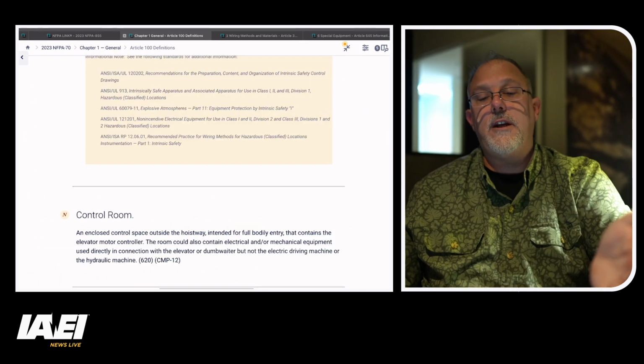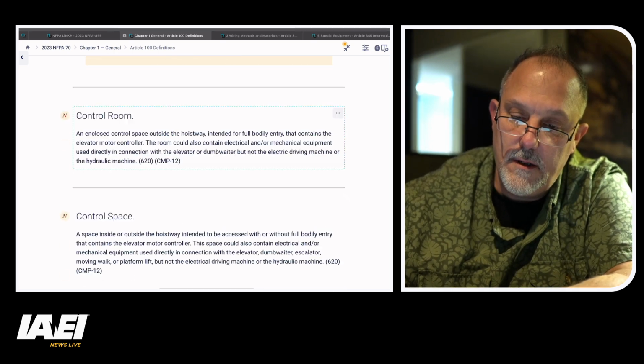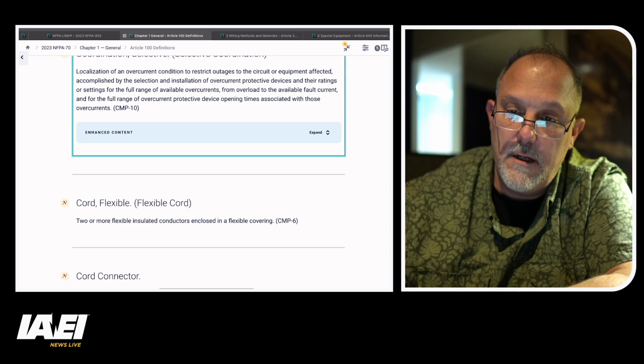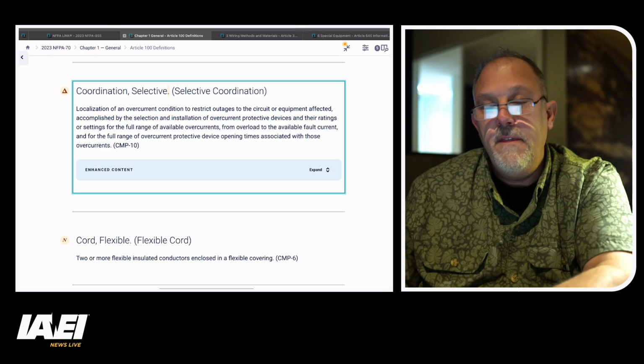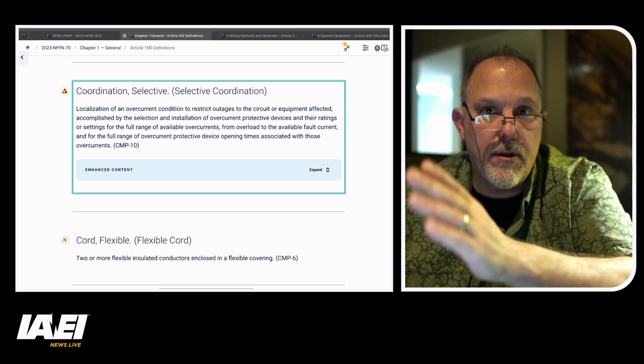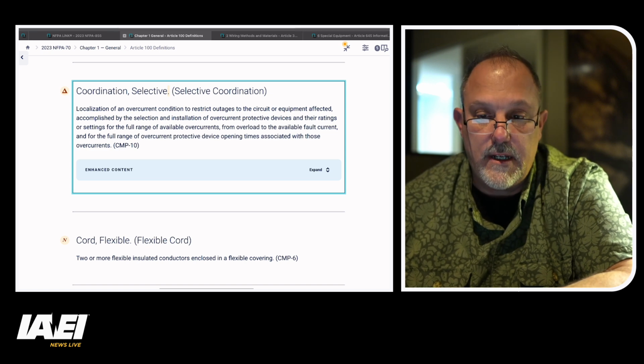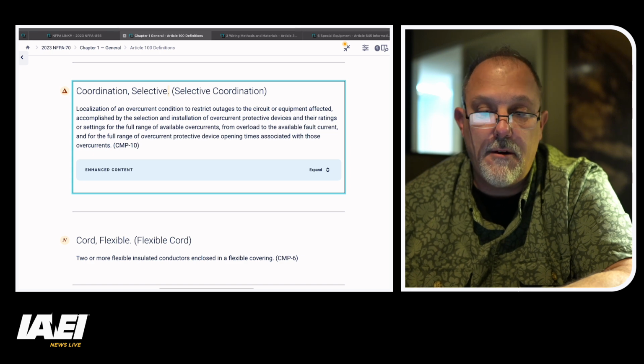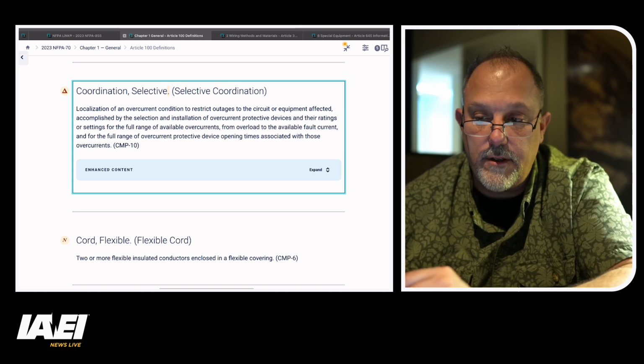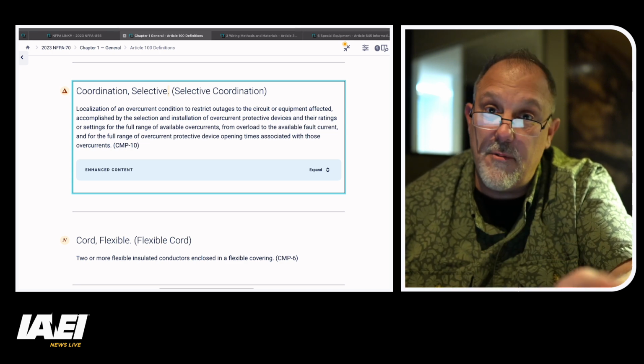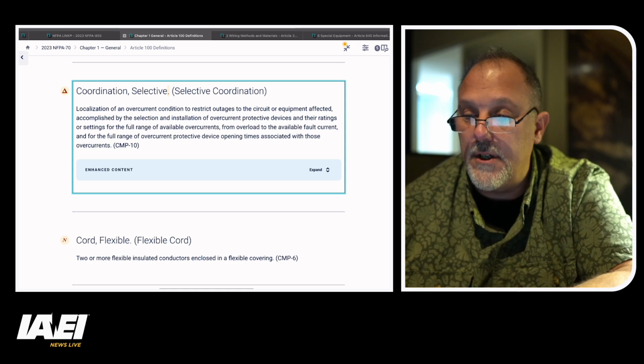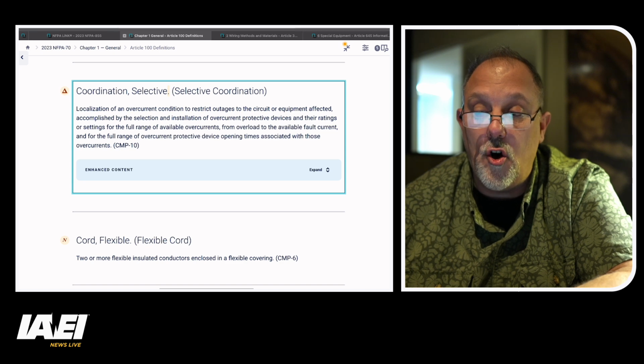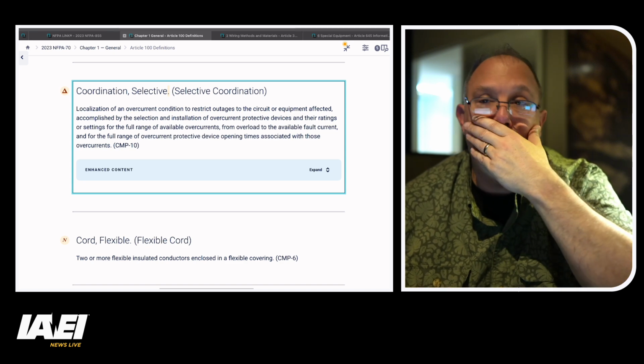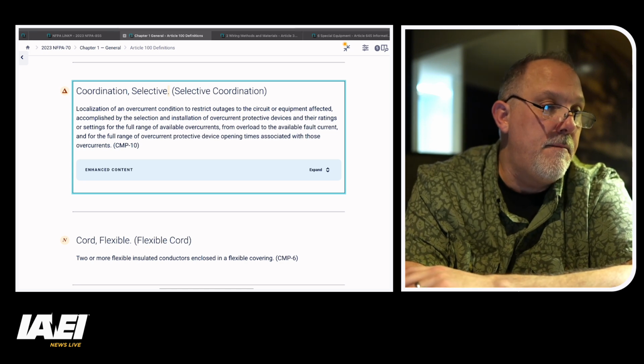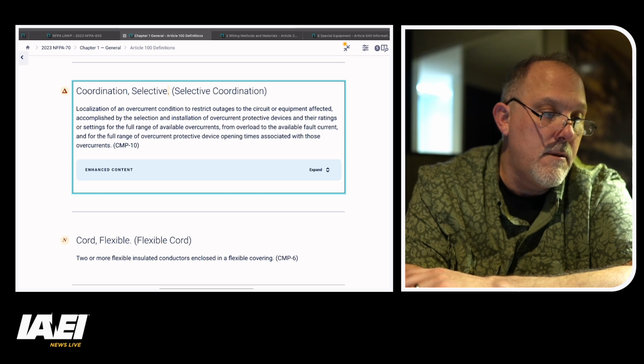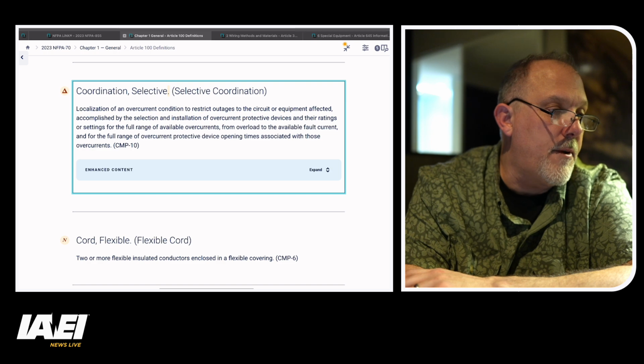That tells us that's the localization. Oh, man. I hate when it does that. Localization of an overcurrent condition, and we know overcurrent conditions are overloads, ground faults, etc., to restrict outages to the circuit or equipment affected, accomplished by the selection and installation of overcurrent protective devices and their ratings or settings for the full range of available fault overcurrents, from overload to the available fault current. And available fault current is another defined term, which is the maximum amount of a fault current, and for the full range of overcurrent protective device opening times associated with those overcurrents. So there it is. I couldn't find it.